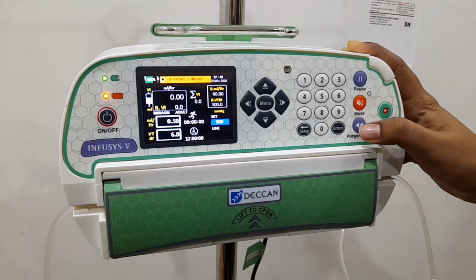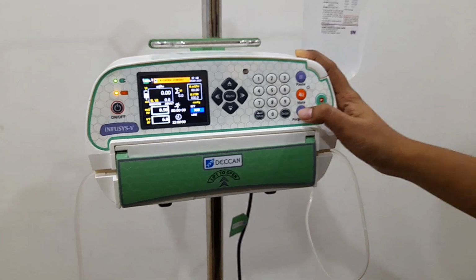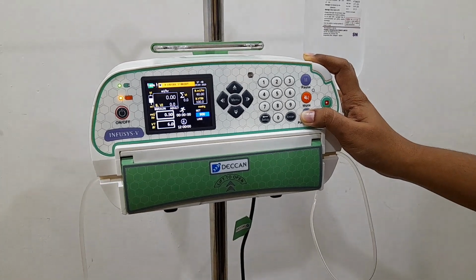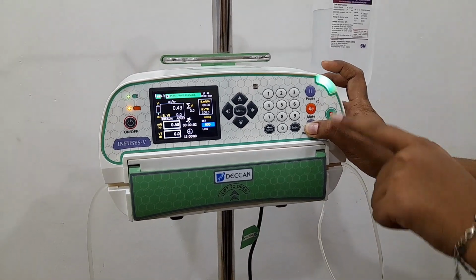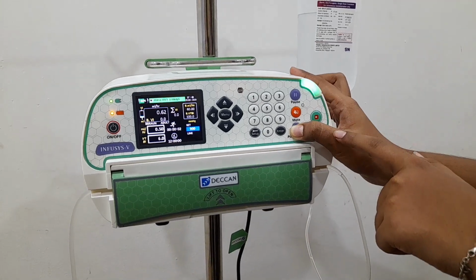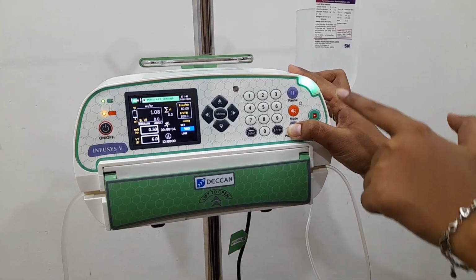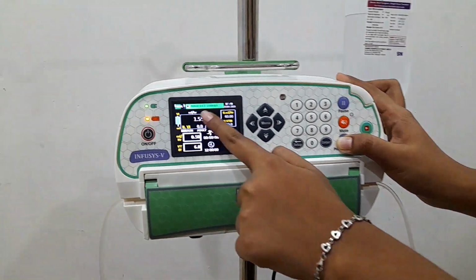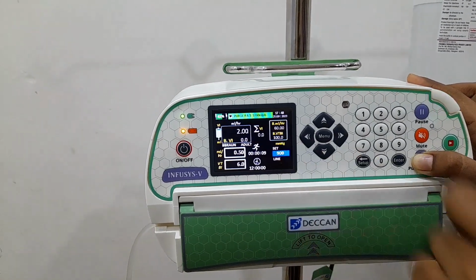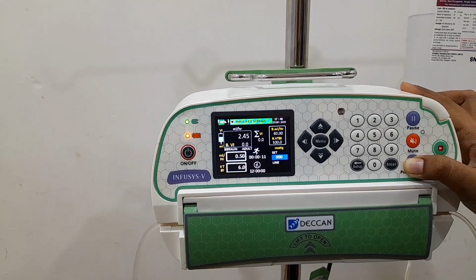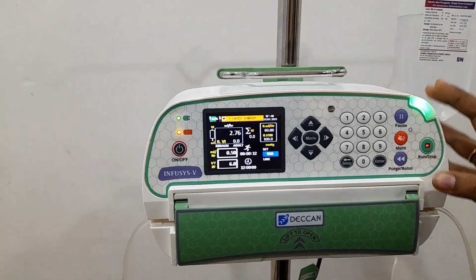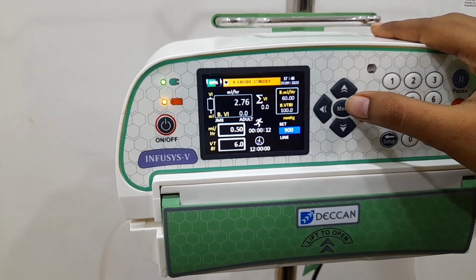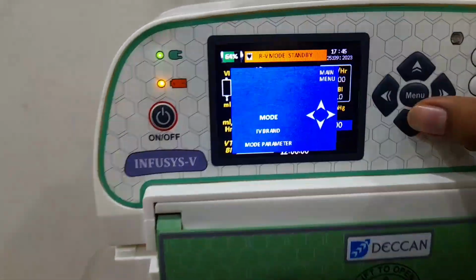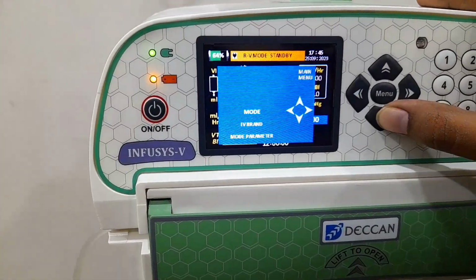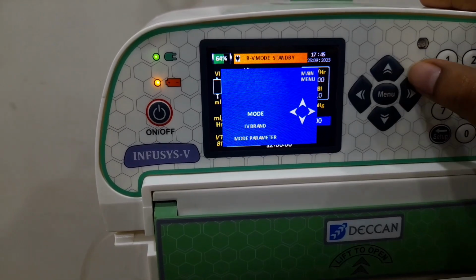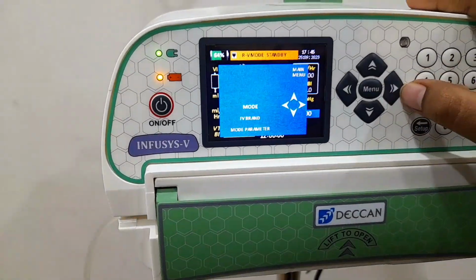Press the purge or bolus key to prime the IV line before starting infusion. Here we can see, by long pressing the purge key, the edge light indication and progress bar as well as status bar. The status bar shows that the purge rate is 1200 ml per hour. Purge can be used only during standby condition. Now let's look at what menu options are given in our pump. Press the menu key and enter the mode using the right navigation key.